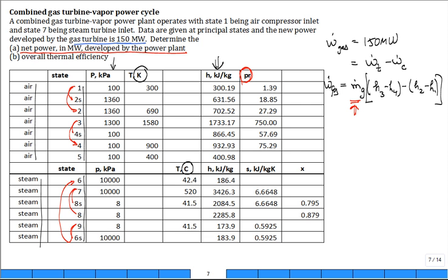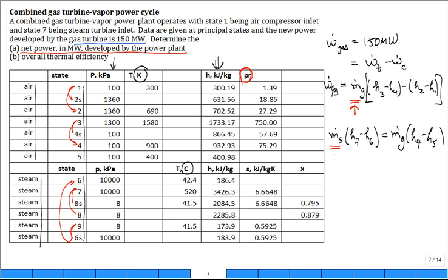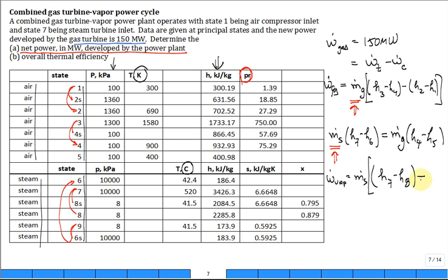You then use the energy balance around the heat exchanger to get the mass flow rate of the steam: M_dot_gas × (h4 − h5) = M_dot_steam × (h7 − h6). Once you know M_dot_gas, you can calculate M_dot_steam. Then W_dot_vapor_net equals the mass flow rate of the steam times the work out of the steam turbine minus what's needed to drive the pump.